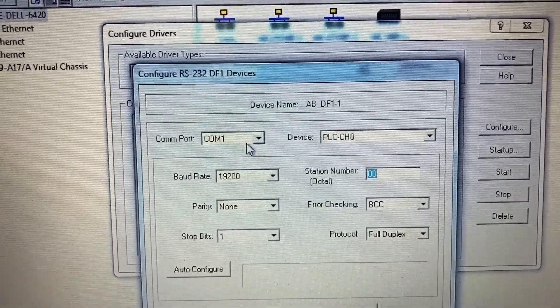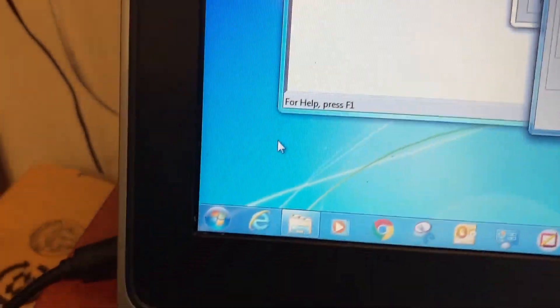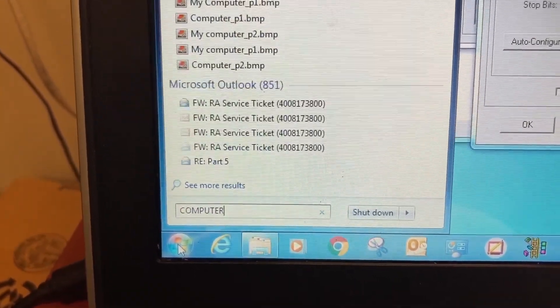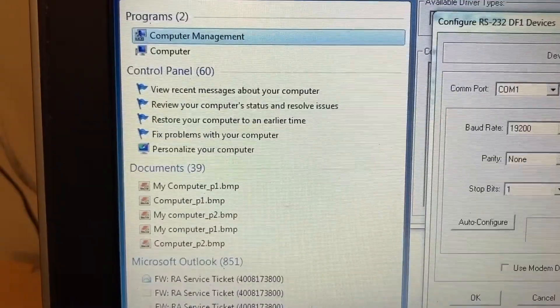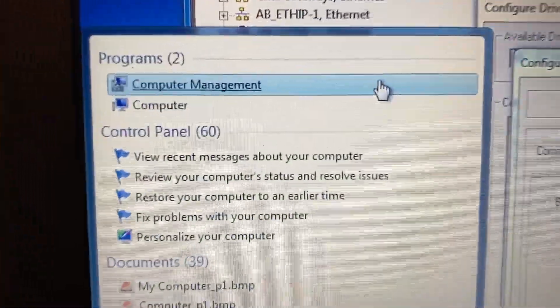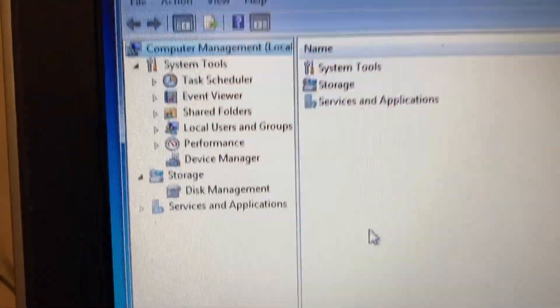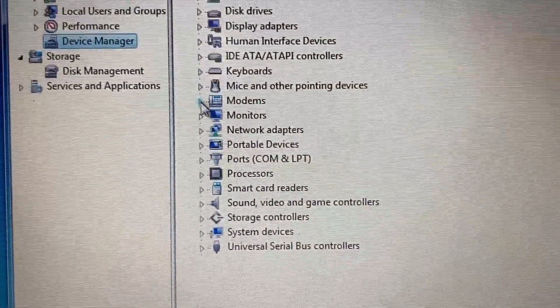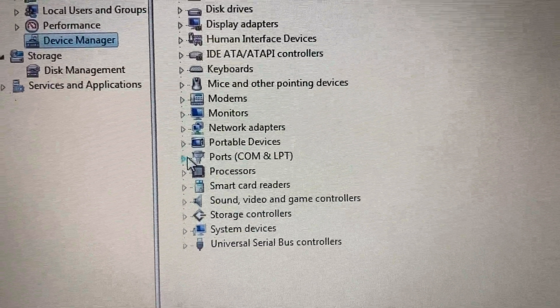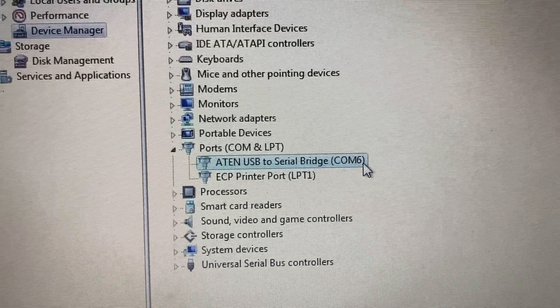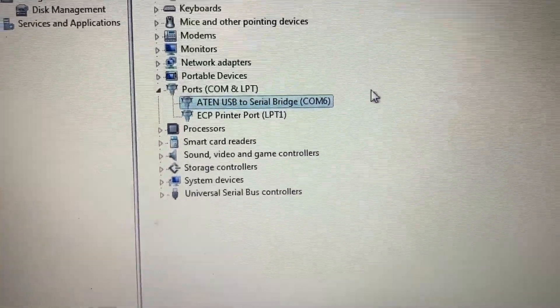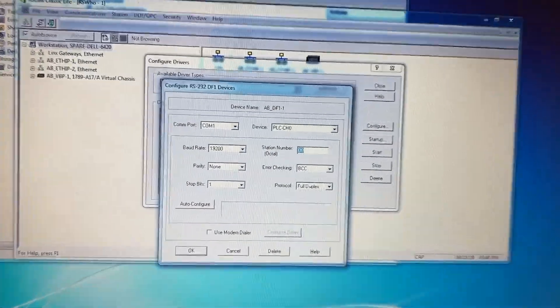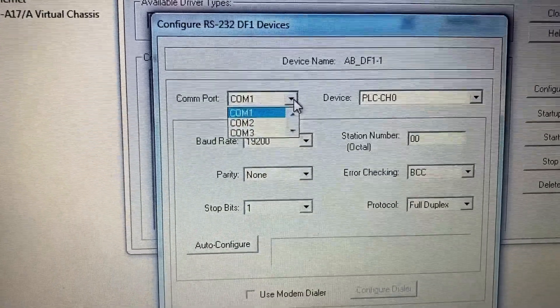To find out what COM port the PLC is connected to on the computer, go to Start, type 'computer', and open Computer Management. In the Computer Management window, select Device Manager and expand Ports. COM6 is the port the PLC is connected to. Go back to RSLinx Classic and select COM6 for the COM port.